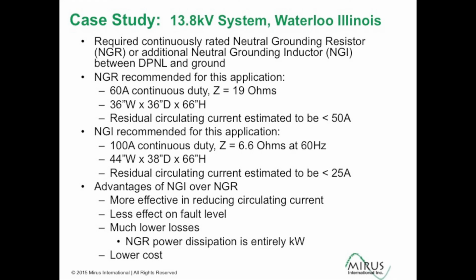So to eliminate or reduce that circulating current, we would require the installation of either a neutral grounding resistor connected back here from the X terminal through to the grounding connection, or a neutral grounding inductor, or NGI, sized to block that extra flow of current. So we went through the calculations to determine that an NGR would require about 19 ohms, would have to have a 60 amp continuous rating. Size of one manufacturer's is shown here, and they predicted there would still be a residual of 50 amps.